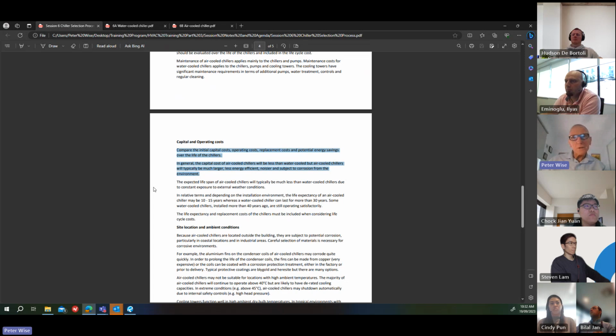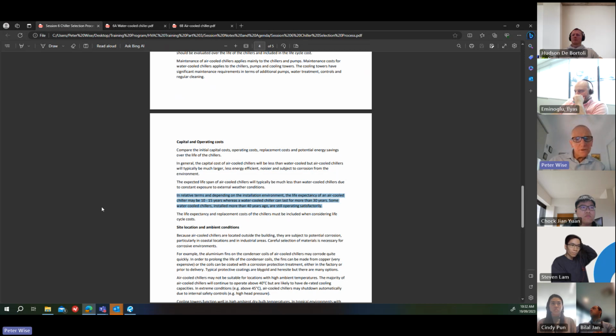99% of the time outside the building, probably 100% of the time they should be. But being outside, they are exposed to the weather. In relative terms, and depending on the installation environment, the life expectancy of an air-cooled chiller may only be 10 to 15 years, whereas a water-cooled chiller can last for more than 30 years. And I've seen some chillers still operating that are 50 years old. Granted, they're not as efficient as you can buy these days, but they're still running.